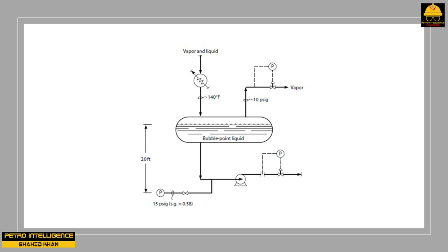The available NPSH to a pump is defined as: the physical pressure at the pump suction minus the vapor pressure of the liquid at the pump suction. To express the available NPSH in feet, measure the pump suction pressure and add the barometric pressure — 14.67 PSIA at sea level. Then look up the vapor pressure of the liquid pumped at the measured pump suction temperature, in PSIA.